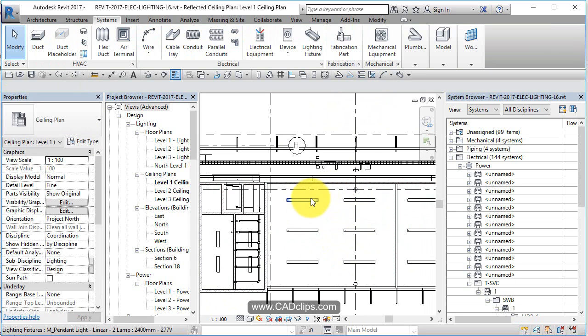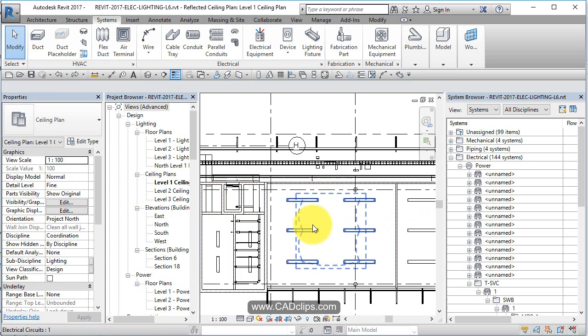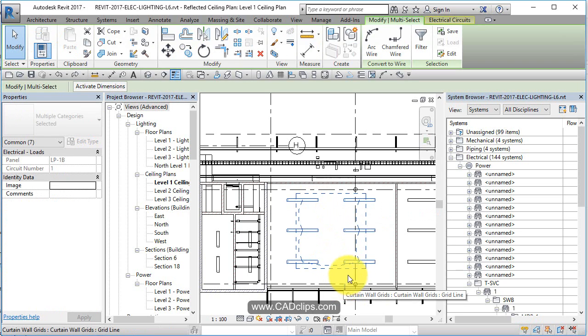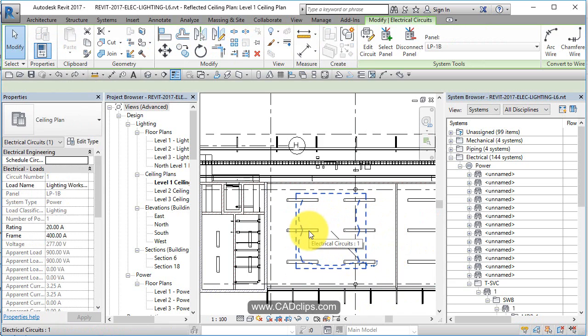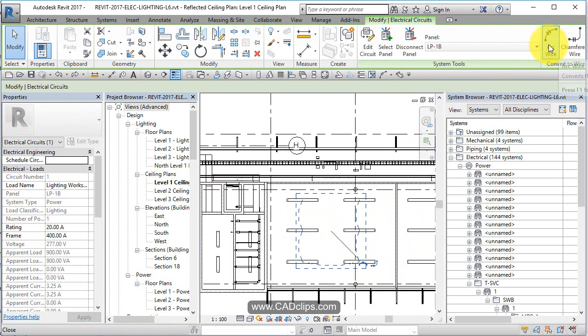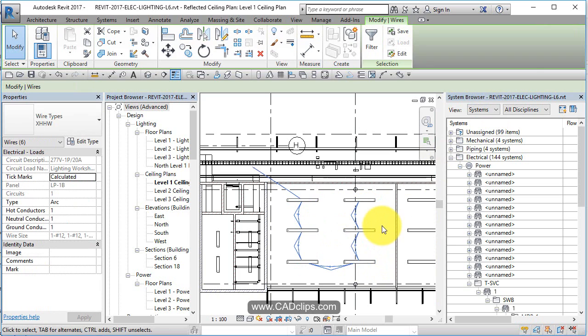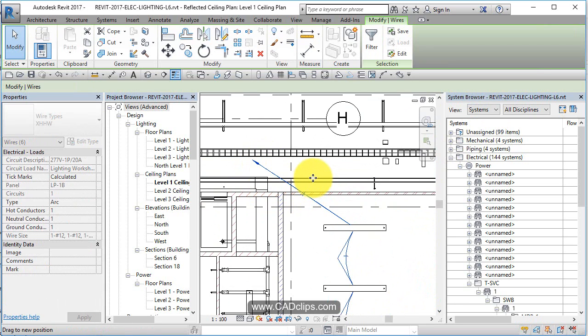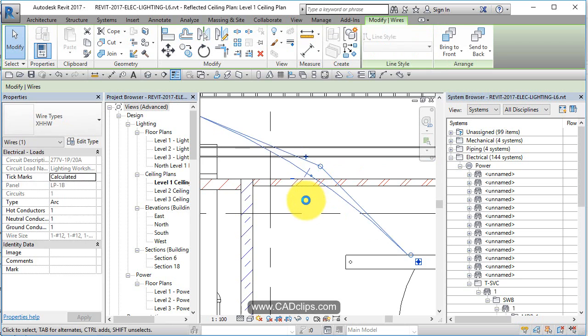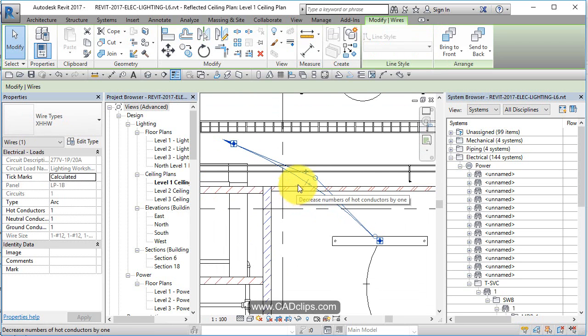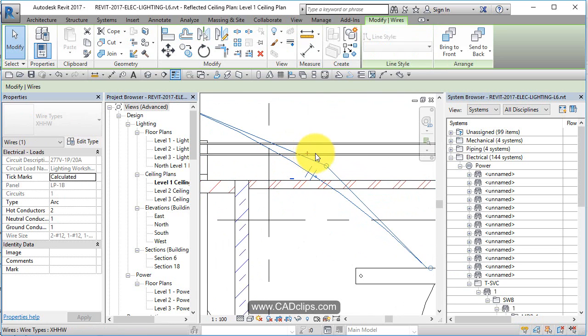To demonstrate: hover over an element — a light or power outlet — then tab and click to select it. You'll see symbols at the bottom or top of the screen. Click 'Arc Wire' and it will create wires to those lights because it knows the circuit. It also adds the home run. One arrowhead means it's a single circuit. You can grab and stretch it, or use plus and minus to add hot conductors.